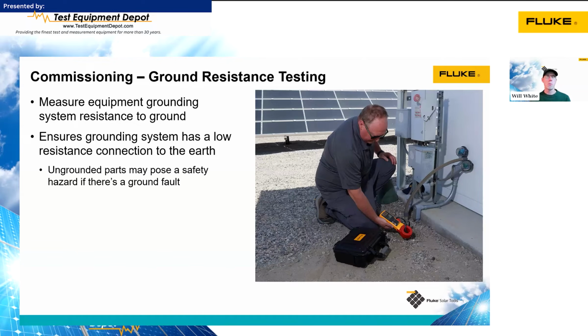If the metal parts aren't properly bonded to ground, we can have issues, safety issues. Also, some overcurrent protection devices won't work properly if they don't have a good path to ground. So we've got a couple tools that can do this, the 1630, the 1625-2. One of them is shown here in this picture that is a stakeless meter. The other one has some stakes, so it measures using a supplemental rod that's included with the test device. So again, making sure that the ground rod is actually bonded to the earth well and there's a good solid connection there.